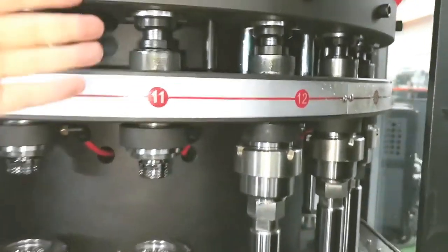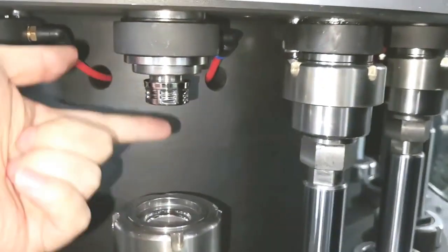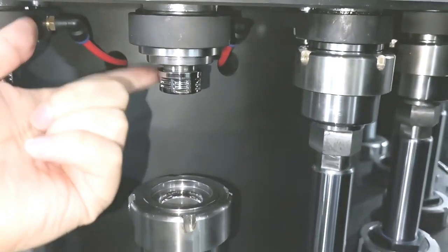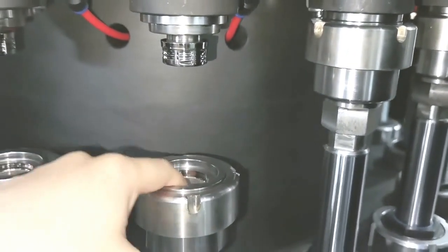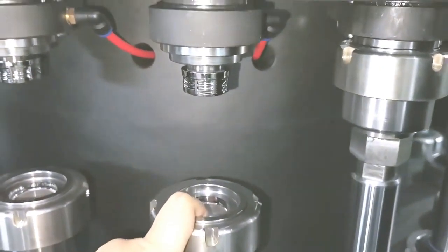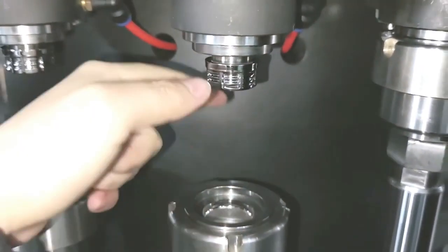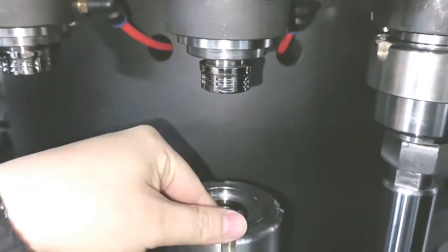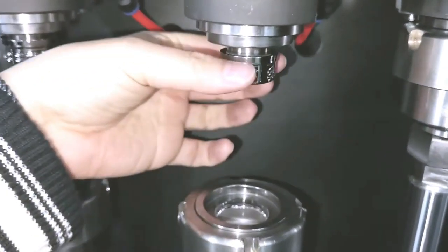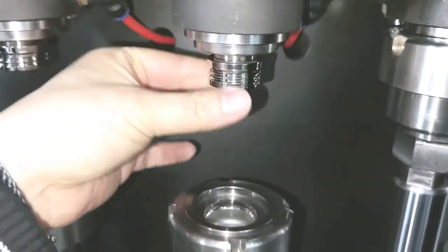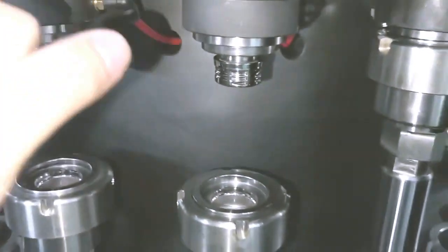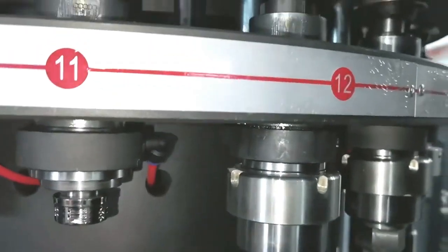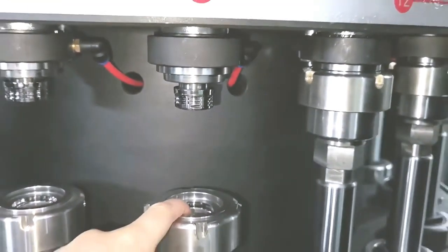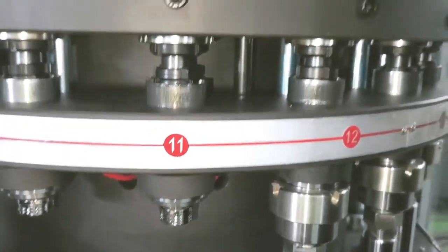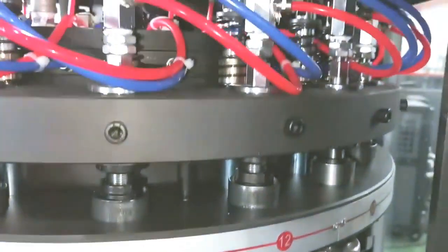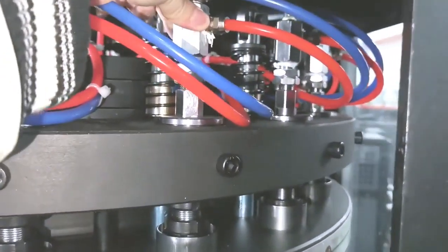Also, if we make it too low, it means every compression this part will touch this other part. In the good situation, these two parts are actually not really touching, because they need to form a gap outside here, so they will not touch. But in this situation, they will touch, and over a long time the motor will get damaged. So we need to adjust this part.